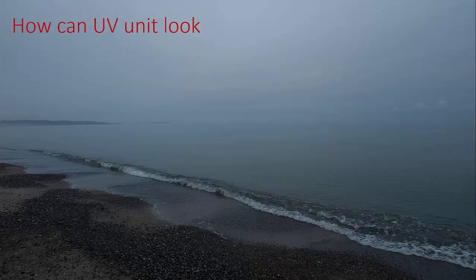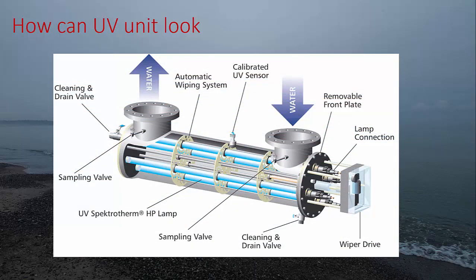How can a UV unit look when you go into a water treatment plant or a wastewater treatment plant? It can look something like this. You see the water coming in, the water going out, and I'm just going to point out two things here. First, the UV sensor. That is very important to control the lamps and basically how well the unit disinfects. Secondly, I just want to make a short note on what is called a wiping system. Basically, wipers that clean off the lamps. This is mainly used for sewage treatment, not so much in drinking water treatment. Then you have other components, which I will not go into.